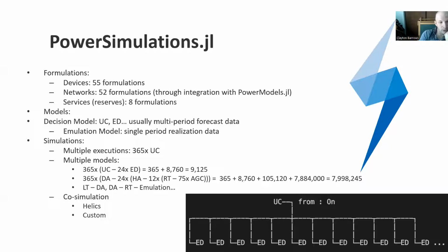So we can do things like unit commitment, economic dispatch, and then things like production cost modeling, where you solve many unit commitment steps and inform subsequent steps with the results of previous steps. We have co-optimization of ancillary services and can do a number of different formulations for power flow, including a number of AC formulations, which result in nonlinear programs, so they're often difficult to solve.